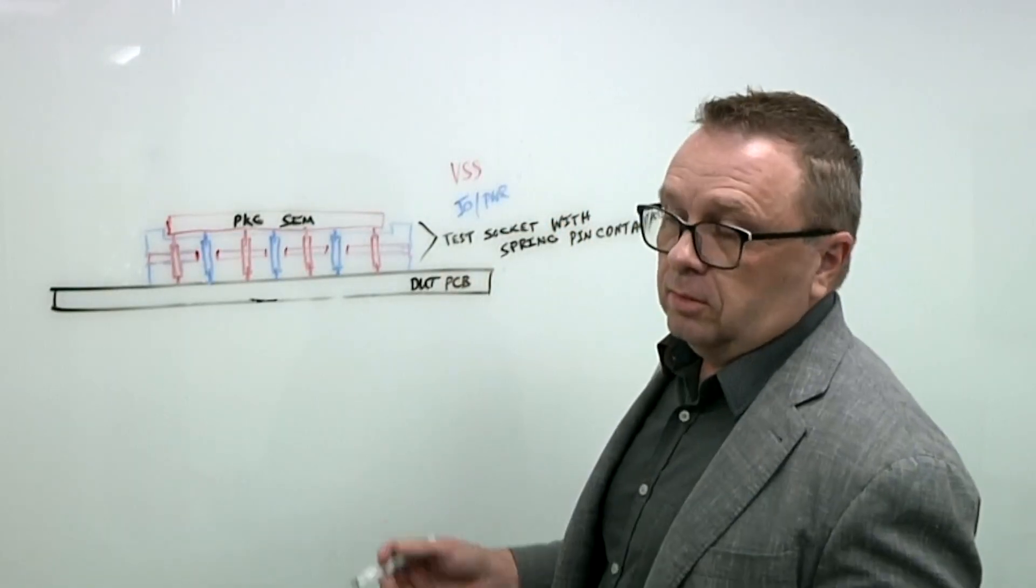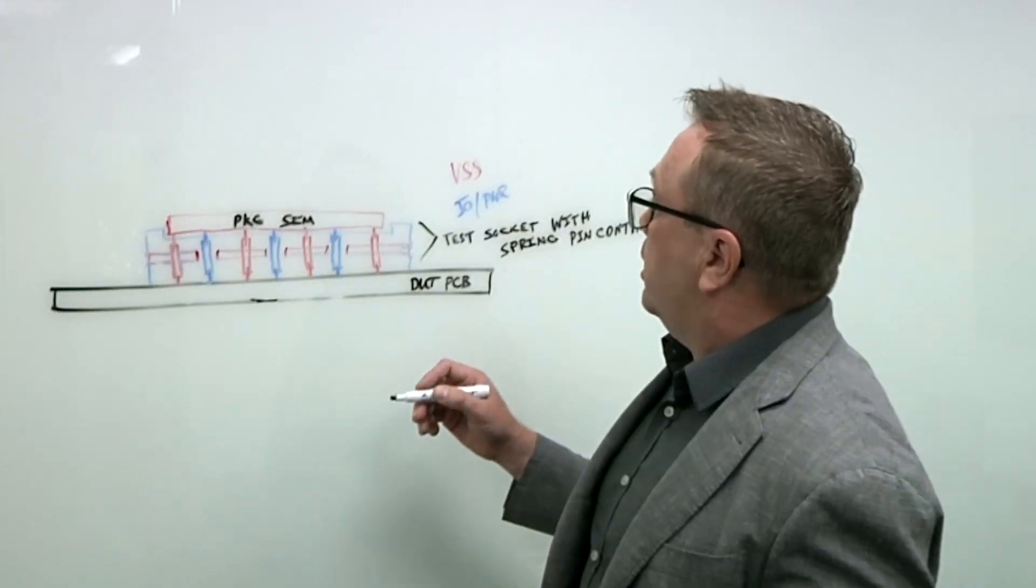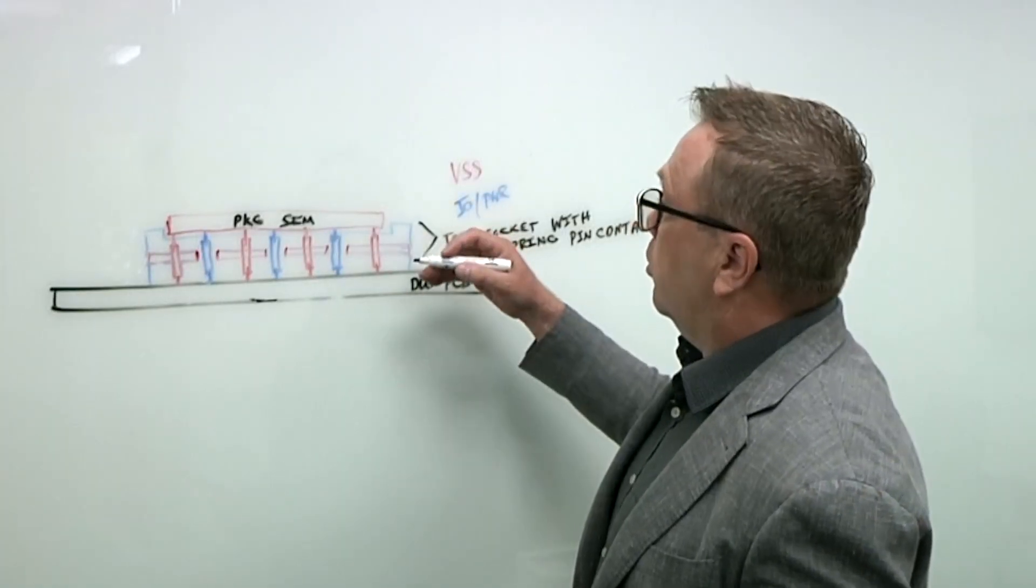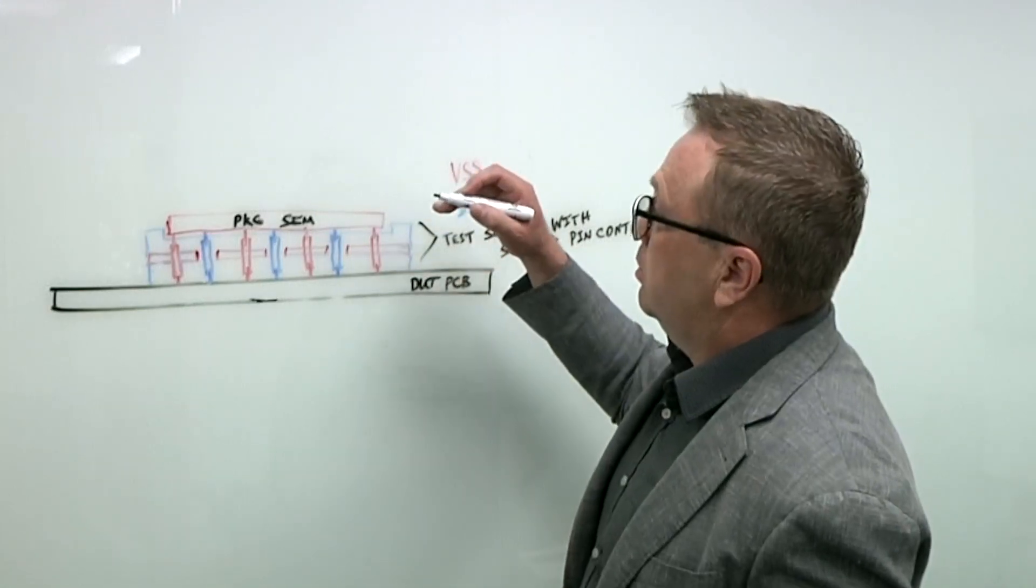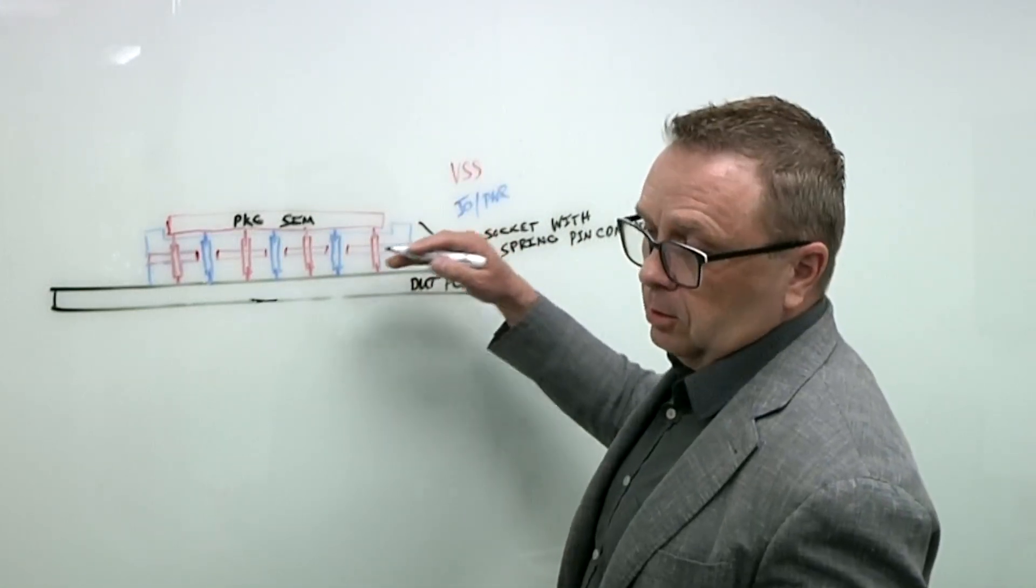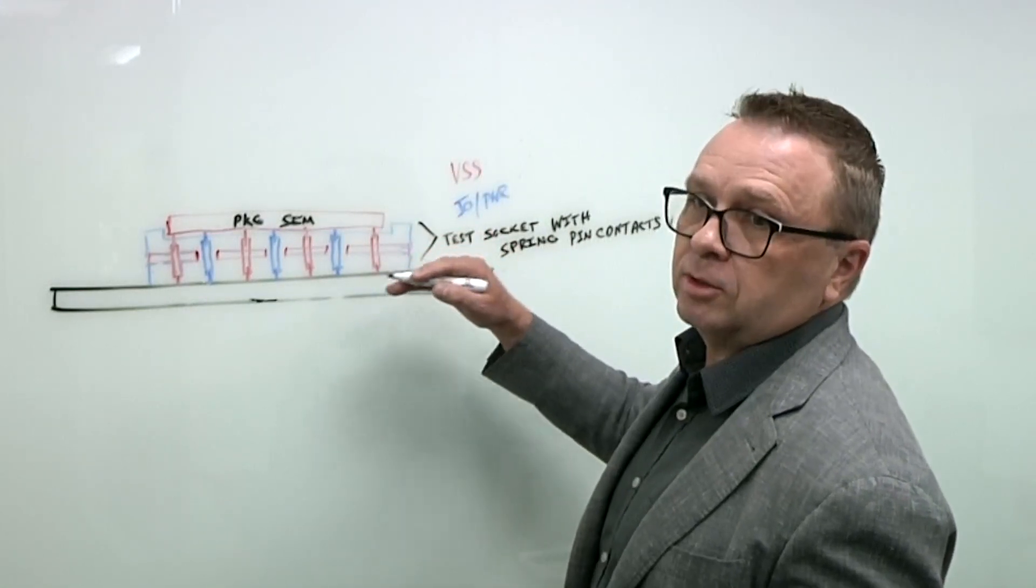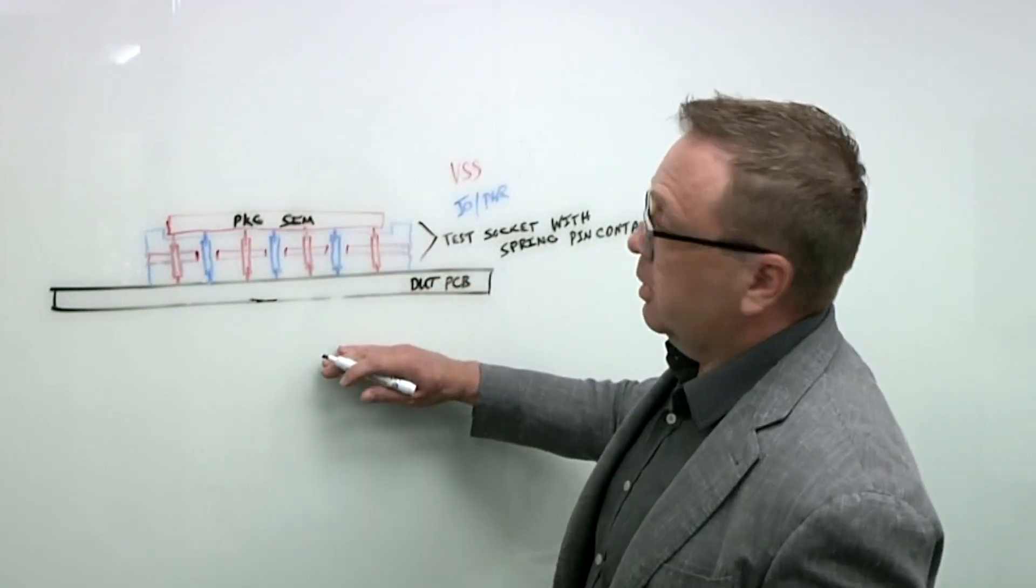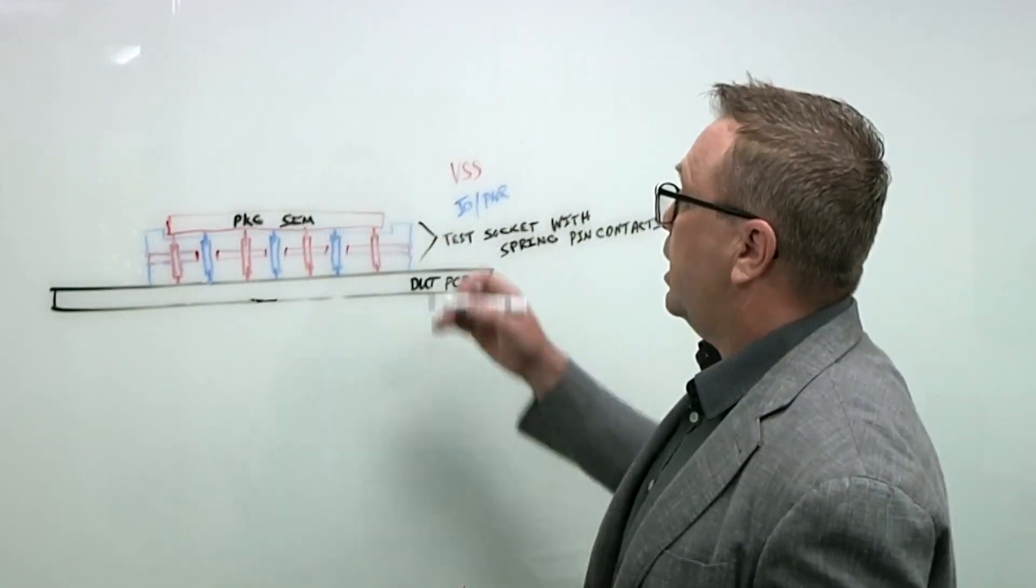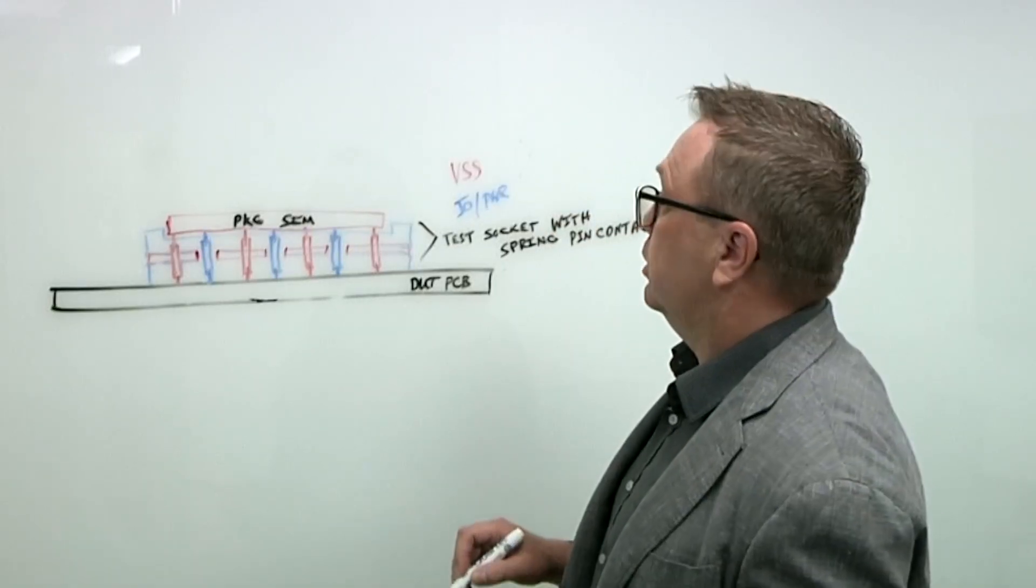With the new advanced AI processors, the performance requirement at system level test requires these packages to be as close to soldered down electrically as possible. Of course, that's not possible. So we have to blind mate electrically interconnect these packages to the tester temporarily to finish the test.